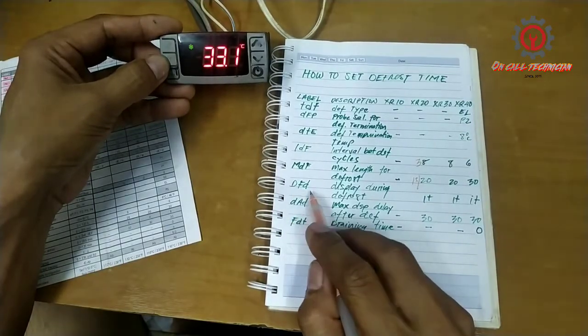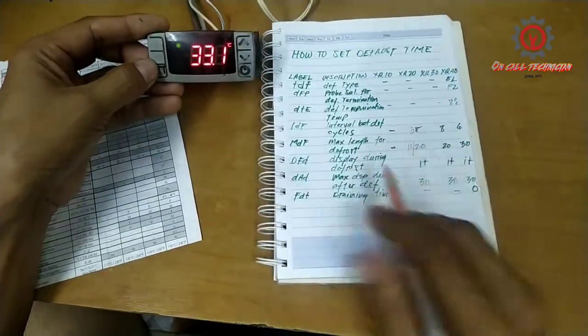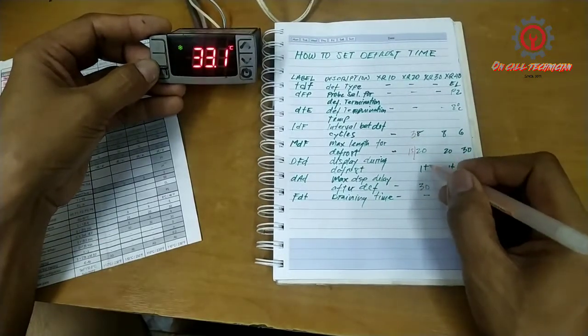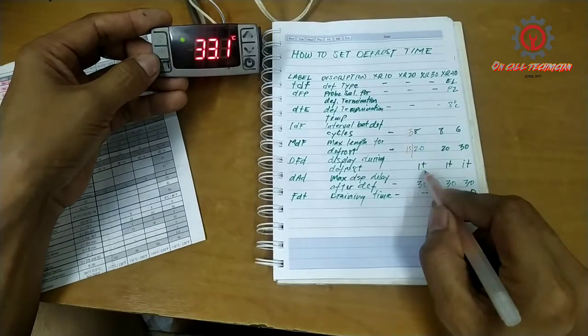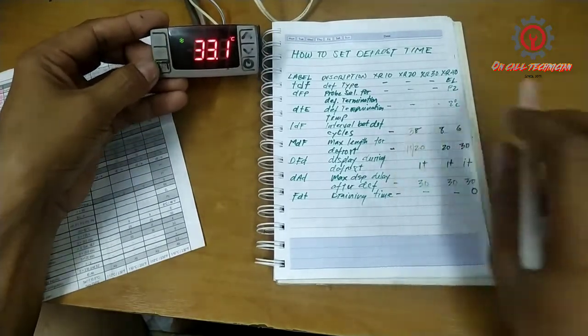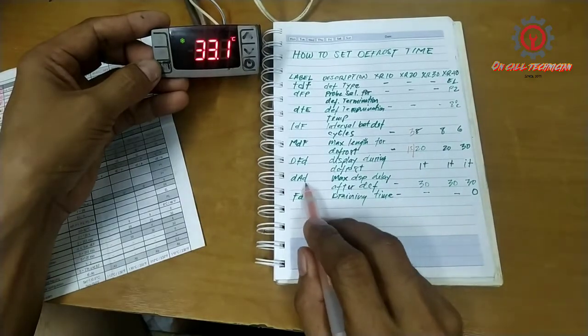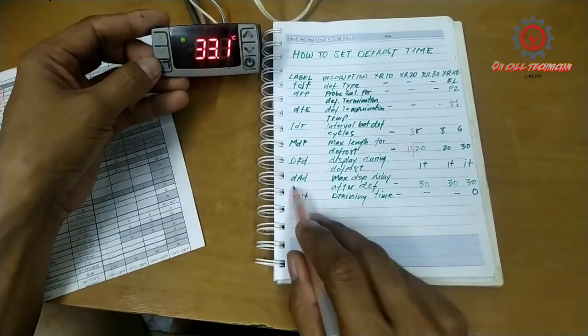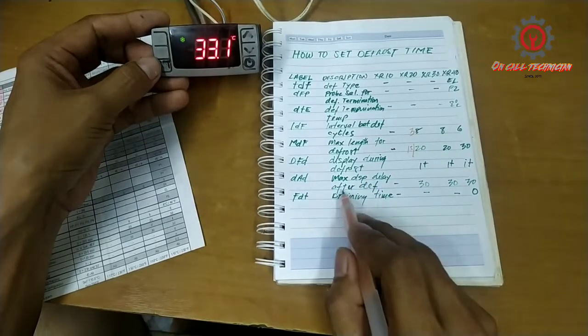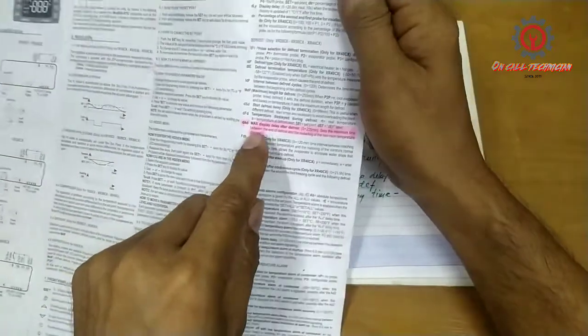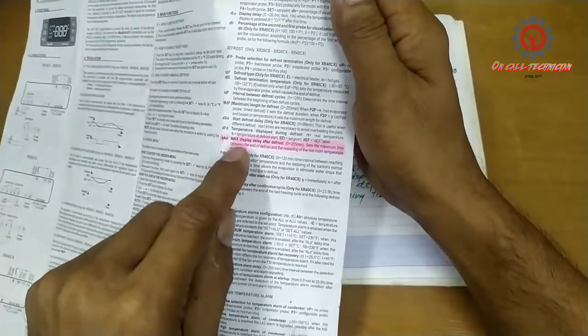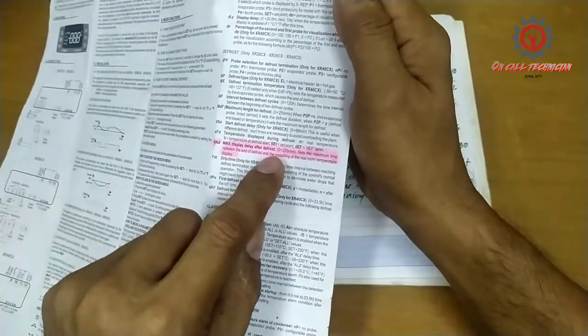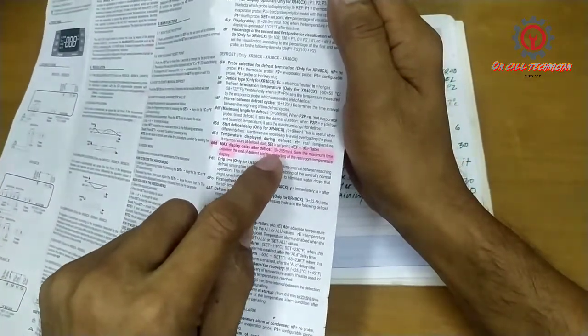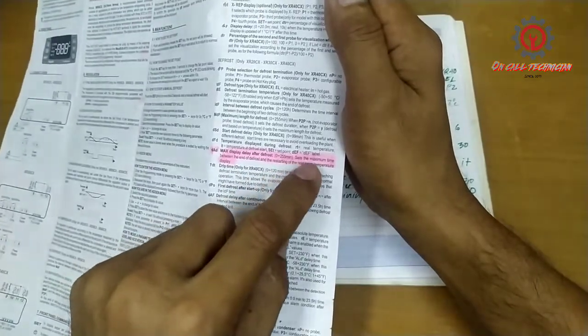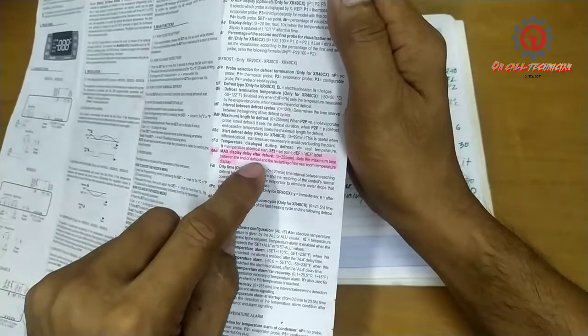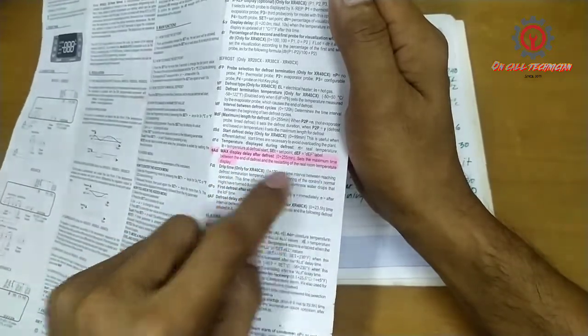For the DFD guys, display during defrost, okay, we have a default of IT, and I'm going to show you what is IT and what is DF here, okay. And for the DAD, this is max display delay after defrost. Here guys, it has the DAD max display delay after defrost. So we have a selection of 0 to 255 minutes, and set the minimum time between the end of the frost and the restarting of the real room temperature display.